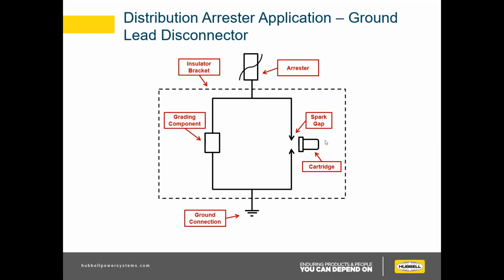this blank 22 cartridge. So it's a rimfire cartridge. When that spark hits the rim of this cartridge, it'll, of course, increase the pressure in the bracket rapidly, and will separate this ground connection from the arrestor. So the arrestor will be taken out of system. Your breaker will operate briefly, so your lights will flicker one time, and then your system will be re-energized. That's why it's important to have a reliable ground disconnector, so your whole line doesn't get locked out because of an arrestor failing.